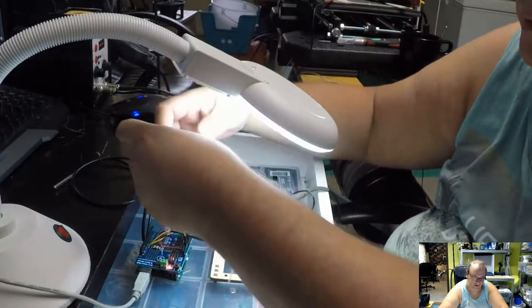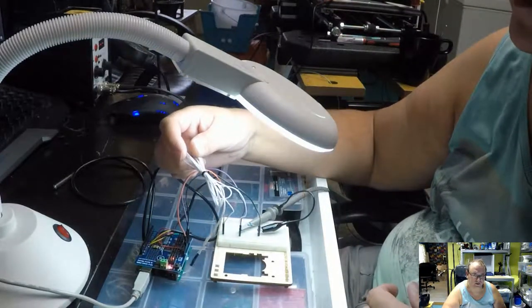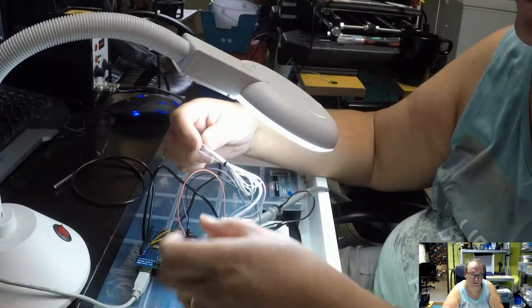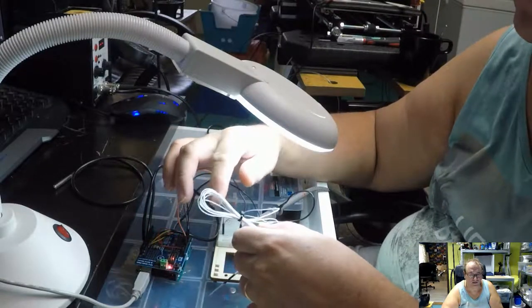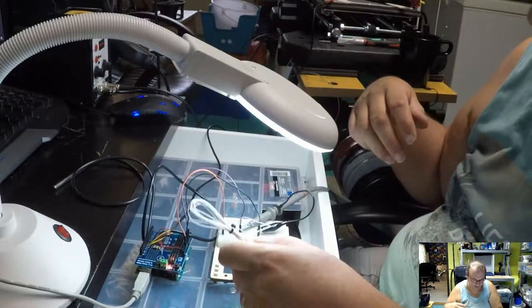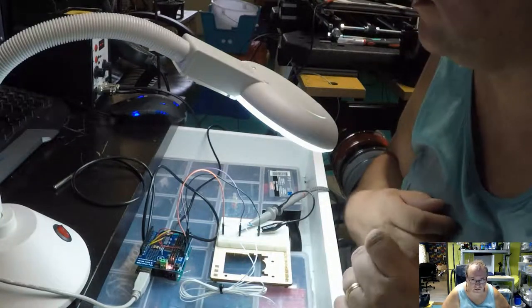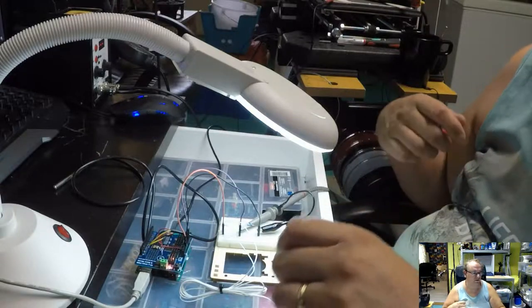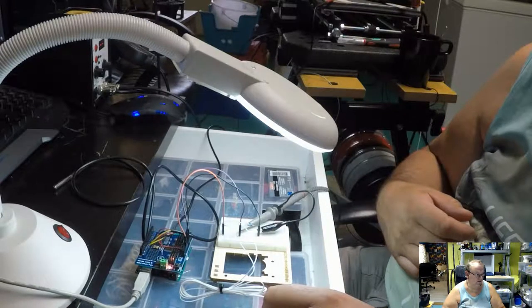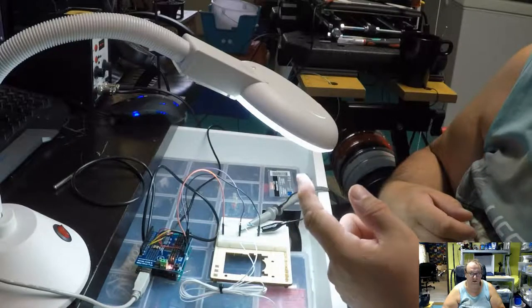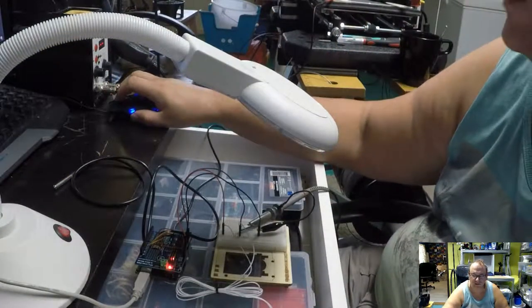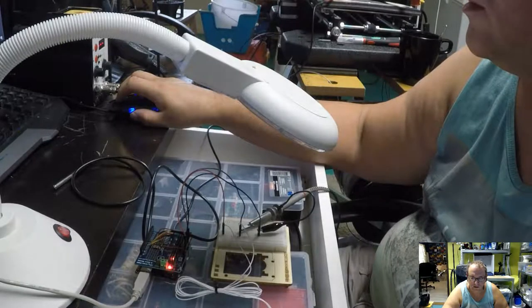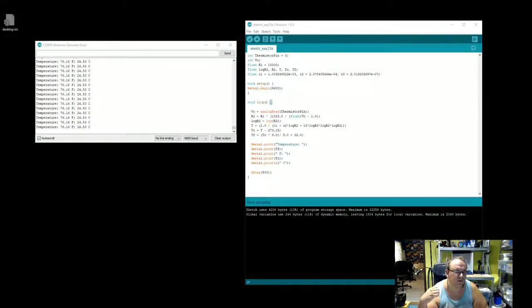Actually, I have this thermistor, and the wire for it is rolled up like this, and then the thermistor is at the end like that. So of course, the natural conclusion is that this is an antenna, so it's picking up interference. The issue was where it could be picking up that kind of low frequency interference. So I actually tested this. I turned that off, and then we go back to here, and then we see the temperature result is stable.